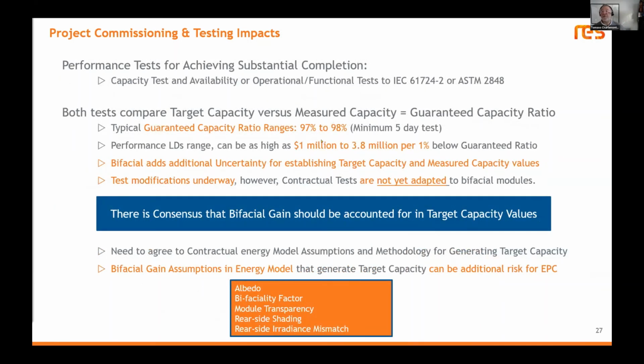So you do your performance testing knowing you have to achieve substantial completion, because that's the trigger to match the date. There are tests you must respect, whether IEC or ASTM, comparing capacity versus measured capacity, which gives the guaranteed capacity ratio — what you promised during engineering, typically between 97 and 98%.